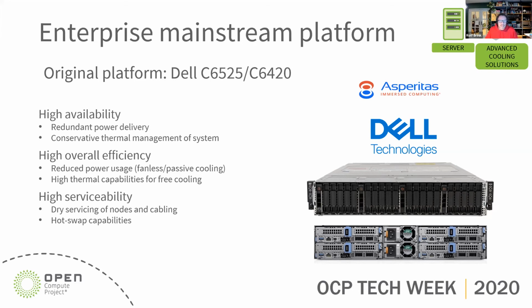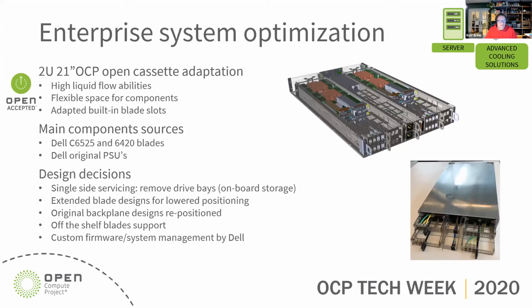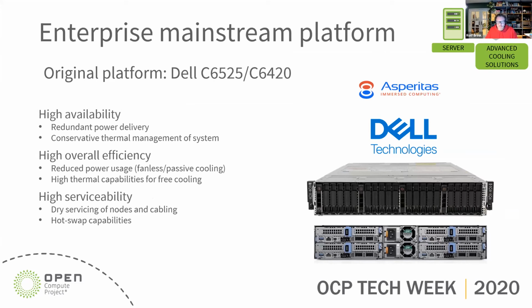Well, here comes one of the first challenges. When you are looking at serviceability and immersion, as mentioned a few times in this presentation lineup, there is only one side of the system that is accessible. If you look back at the original system, one side of this platform is equipped with hard drives, and the other side with blades. If you're going to put this in vertically in an immersion tank, one of these sides will not be accessible for hot servicing, so you have to choose which side is more relevant for servicing.